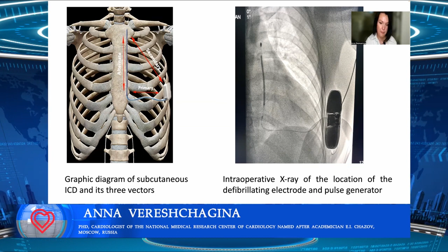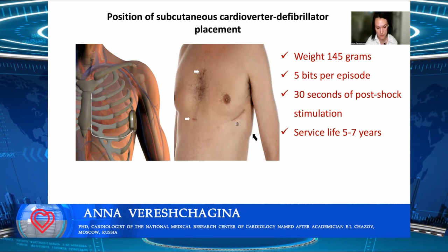The generator can deliver up to 5 high-energy, non-programmable defibrillation impulses per episode and anti-bradycardia pacing at a rate of 50 beats per minute for 30 seconds. Post-shock pacing is provided if asystole of more than 3.5 seconds is detected. The estimated lifespan of the third-generation subcutaneous ICD was 5 years, while of the latest models it exceeds 7 years. Furthermore, remote monitoring of the device is now available for the new model of subcutaneous ICD.